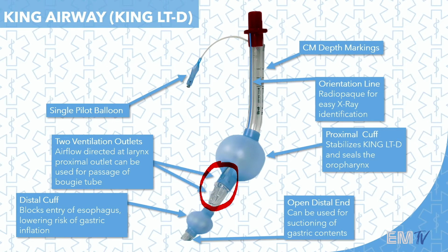There are 2 ventilation outlets located on the anterior of the device. These are directed toward the larynx. The larger, more proximal outlet you can actually place a bougie tube into, or a bronchoscopy device, and actually use that outlet as well. The distal cuff down here blocks the entry of the esophagus, basically closes off the esophagus, lowering the risk of any sort of gastric inflation or vomiting. And unlike previous incarnations of the King Airway, the distal end here was left open so that you can actually pass a French suction tube down into the stomach and decompress the stomach during CPR, or simply to suction.